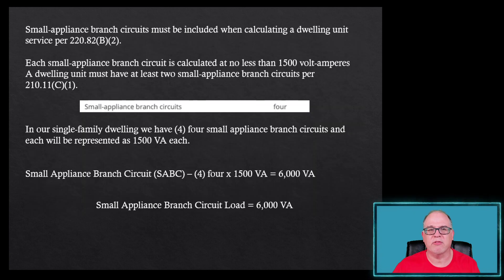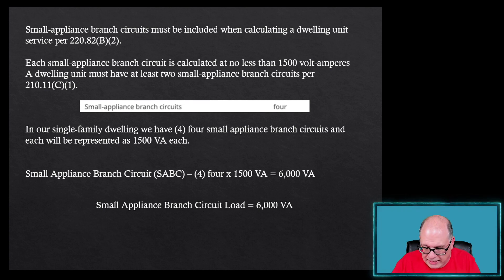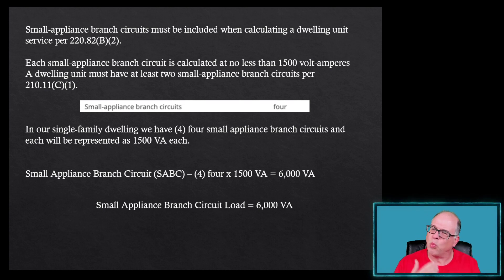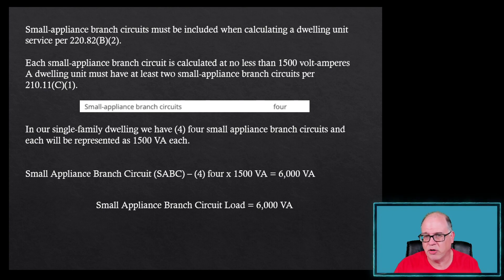When doing the small appliance calculation, as you can see in 220.82B2, we know that 210.11(C)(1) requires at least two small appliance branch circuits. In our case, we've got four. Each small appliance branch circuit is 1,500 VA. Since we've got four of them, we do four times 1,500 — that's 6,000 VA. So our small appliance branch circuit load is 6,000 VA.